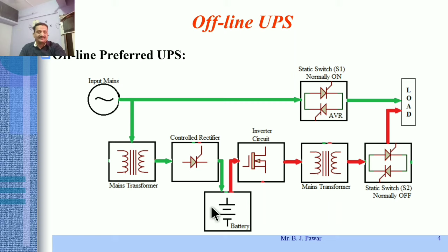Already you learned about this inverter, how we can convert DC to AC by using thyristors. Mostly quasi-square inverters are preferred in such applications, and that converted AC, through the transformer, is coupled to the load, and the load gets power. Again, whenever there is availability of the input mains power supply, automatically this static switch S2 gets turned off, and static switch S1 gets activated so that the power is delivered directly to the load, correct? And again charging of the battery takes place like this.